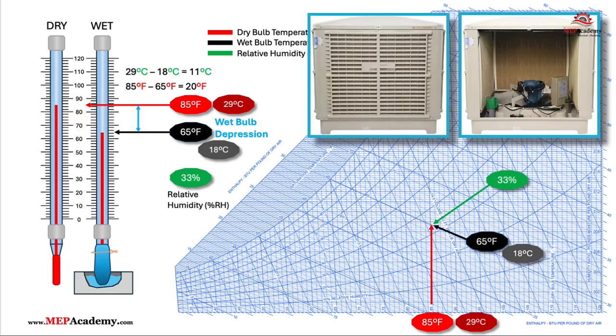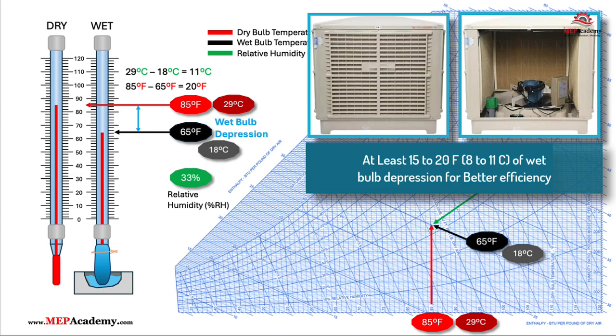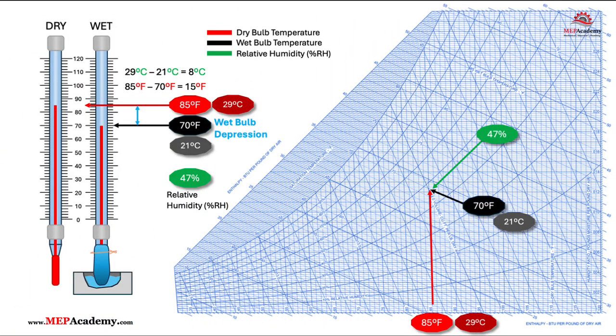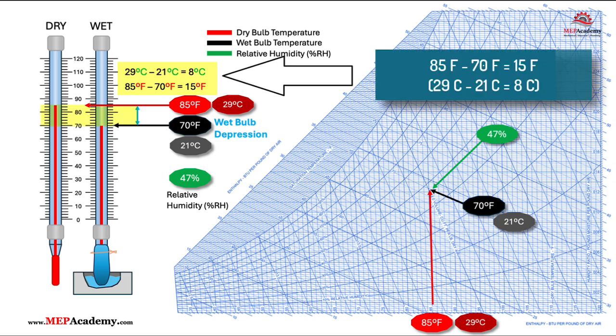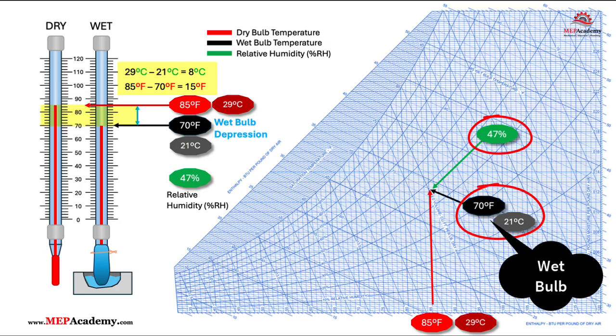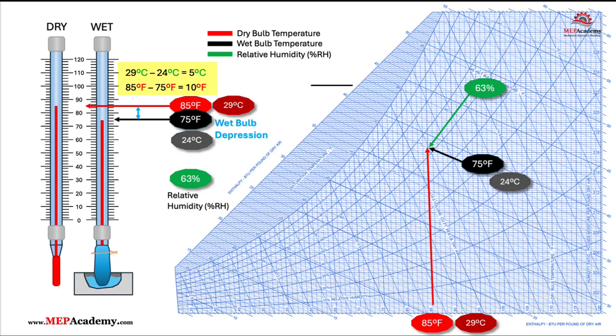For efficient use of a swamp cooler or evaporative cooler, a wet bulb depression of at least 15°F to 20°F (8 to 11°C) or more is generally required. This means the difference between the dry bulb temperature and the wet bulb temperature should be at least 15°F (8°C), indicating low enough humidity for effective evaporation and cooling. Evaporative cooling is best suited for hot, dry climates with low humidity. With a 15°F (8°C) wet bulb depression, the relative humidity has reached 47% at a 70°F (21°C) wet bulb. With a 10°F (5°C) wet bulb depression, the relative humidity has reached 63% at a 75°F (24°C) wet bulb.